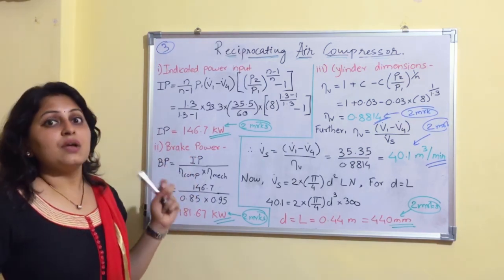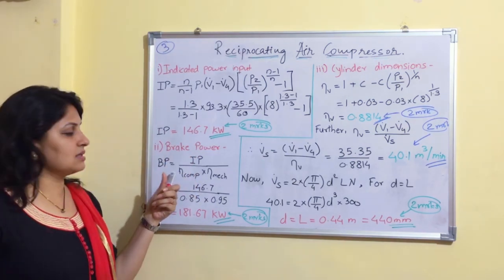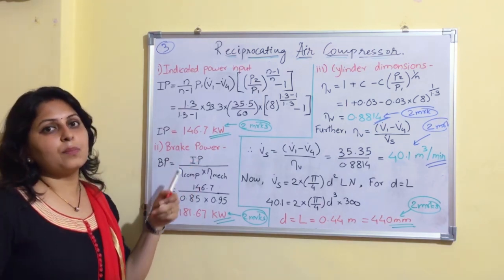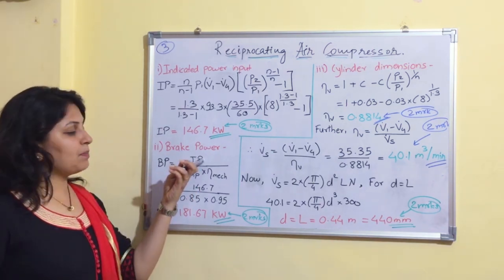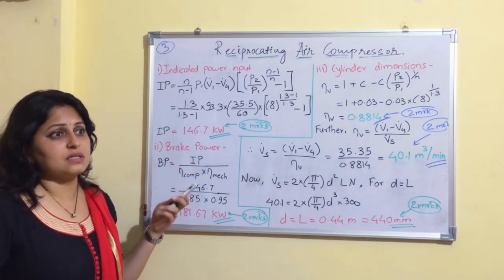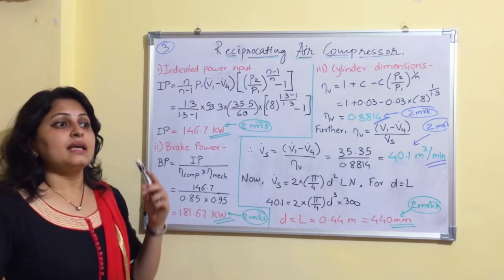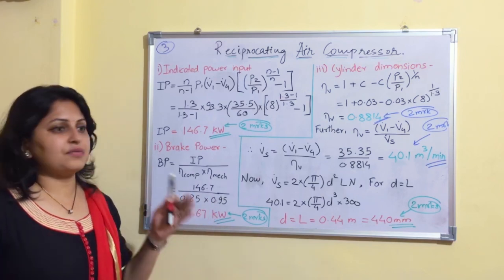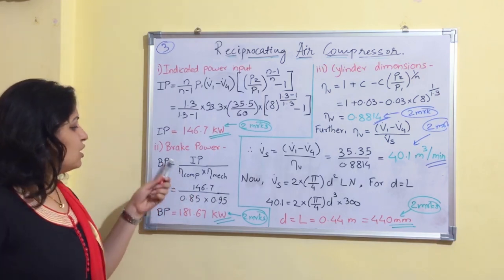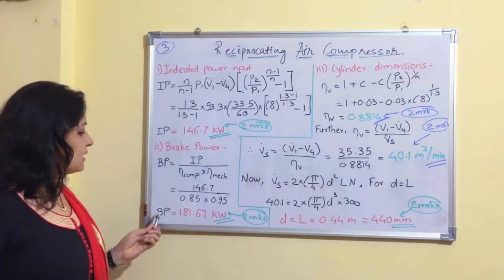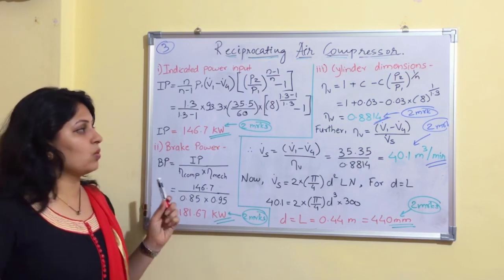The next term is brake power. Since mechanical efficiency = indicated power / brake power, we get brake power = indicated power / (mechanical efficiency × compressor efficiency). Dividing by both efficiencies (0.85 × 0.95), we get brake power = 181.67 kW.